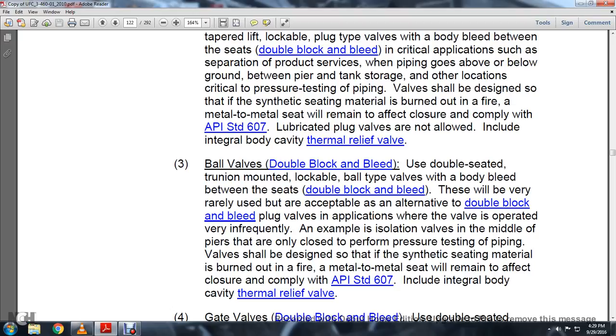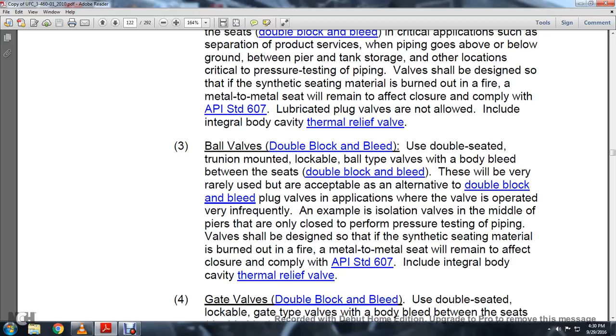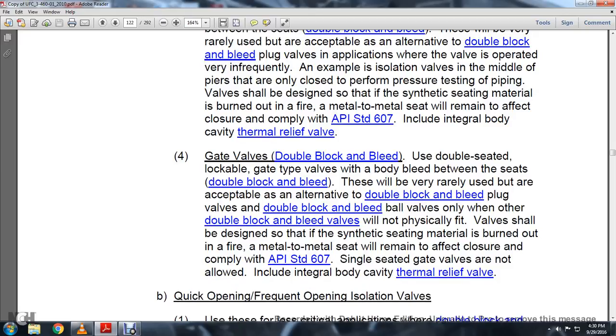The valve should be designed so that the synthetic seating material is burned out in a fire and a fire metal to metal seat will remain effective. The closure shall comply with API standard 607, including the integral body cavity thermal relief valve.